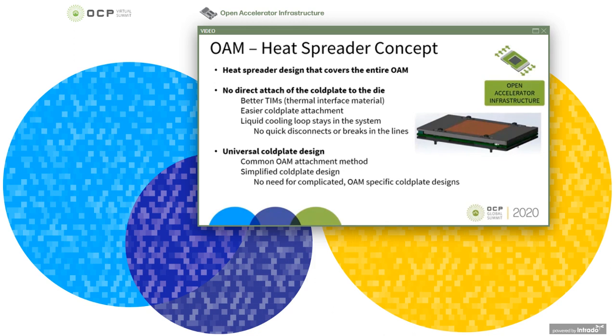It also provides easier cold plate attachment that could potentially be universal. And it does not require the liquid cooling loop to be broken, since the loop can stay inside the system. There are no quick disconnects or required breaks in the cooling lines for this concept.